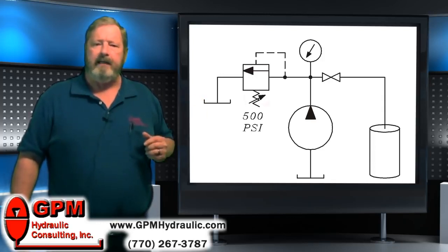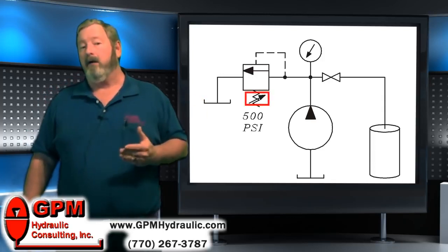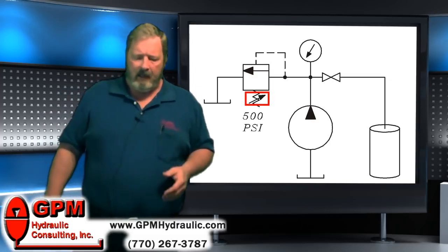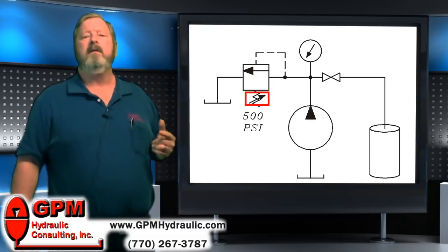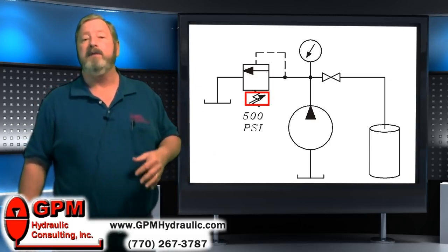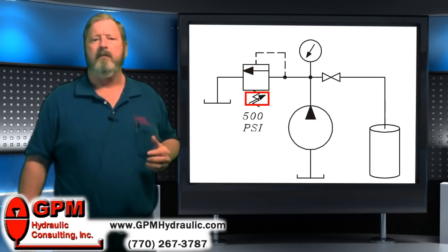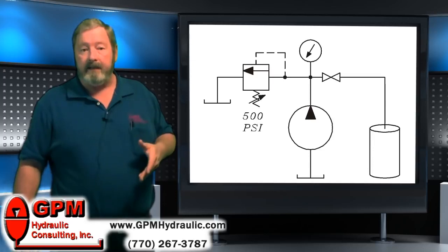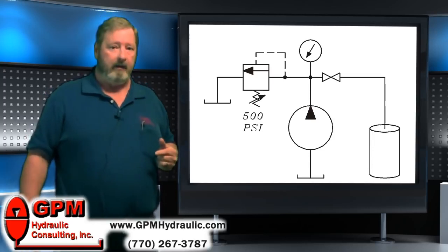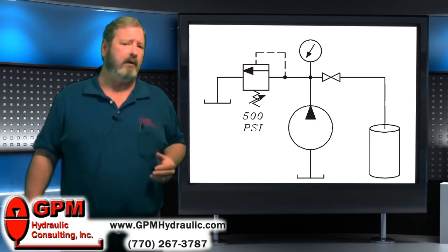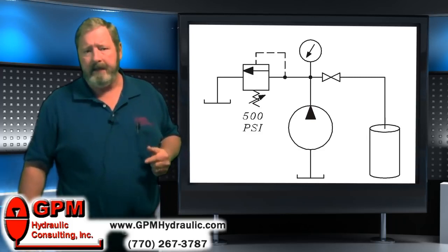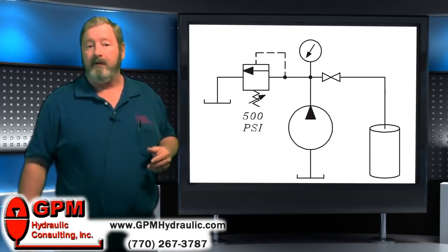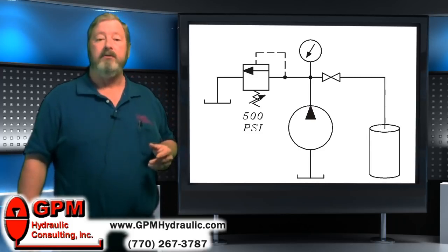Notice on the spring that there's a 45-degree angle arrow going through the spring. A 45-degree angle arrow means that a component is variable or adjustable in some fashion. More often than not, it means that there is a knob on that component, something for the knob turner to get his mitts on. Every plant has a knob turner, right? Knob turner's name is usually not me.